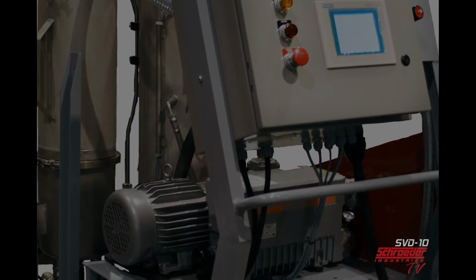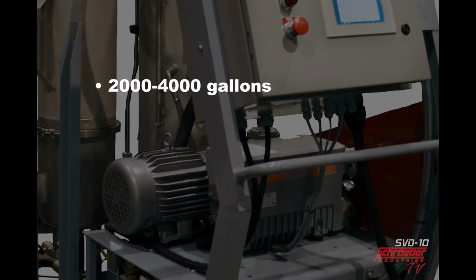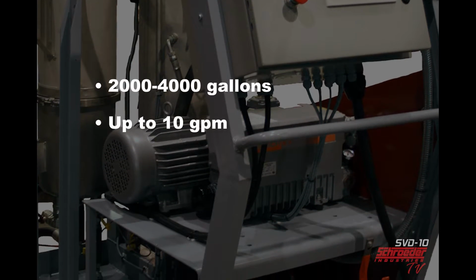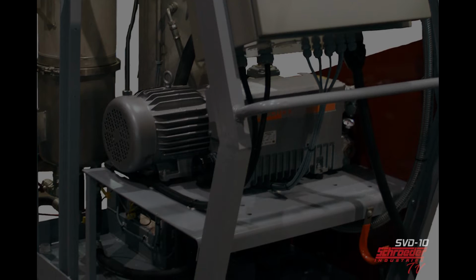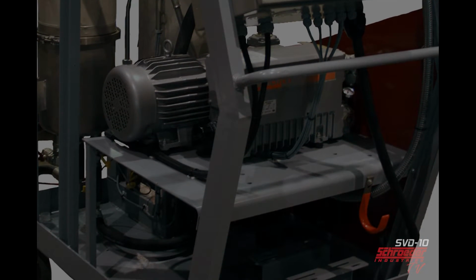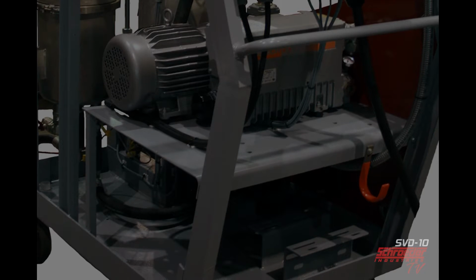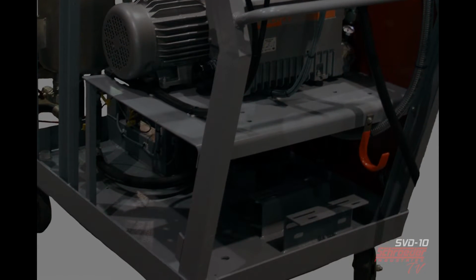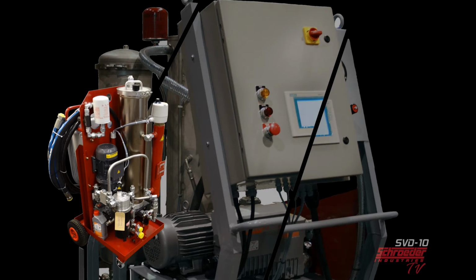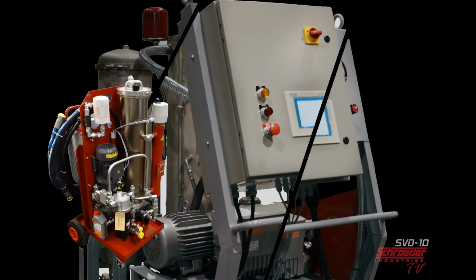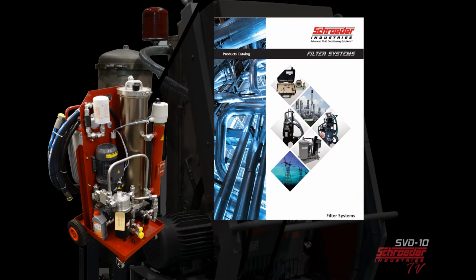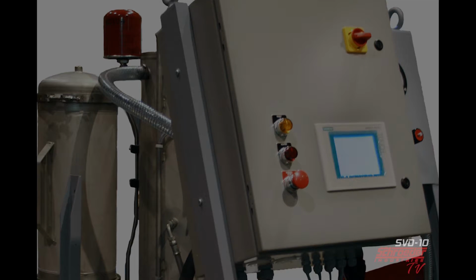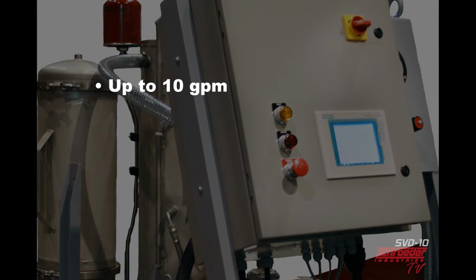The SVD10 can be used for tank volumes from 2,000 to 4,000 gallons with its flow rate of up to 10 GPM. The SVD10 offers customization options to build a vacuum dehydrator that best works for you. In addition to the SVD10, we offer the SVD01, the SVD05, the SVD16, and the SVD23 models. Again, if you'd like exact specifications on the SVD05, 16, or 23, please reference our filter systems product catalog.